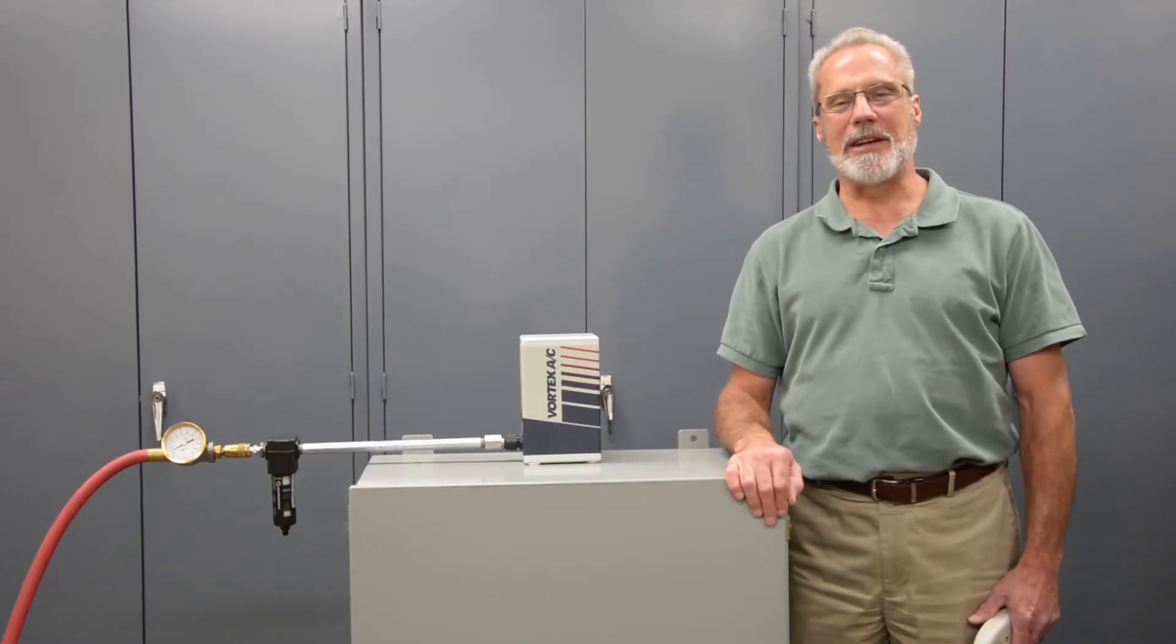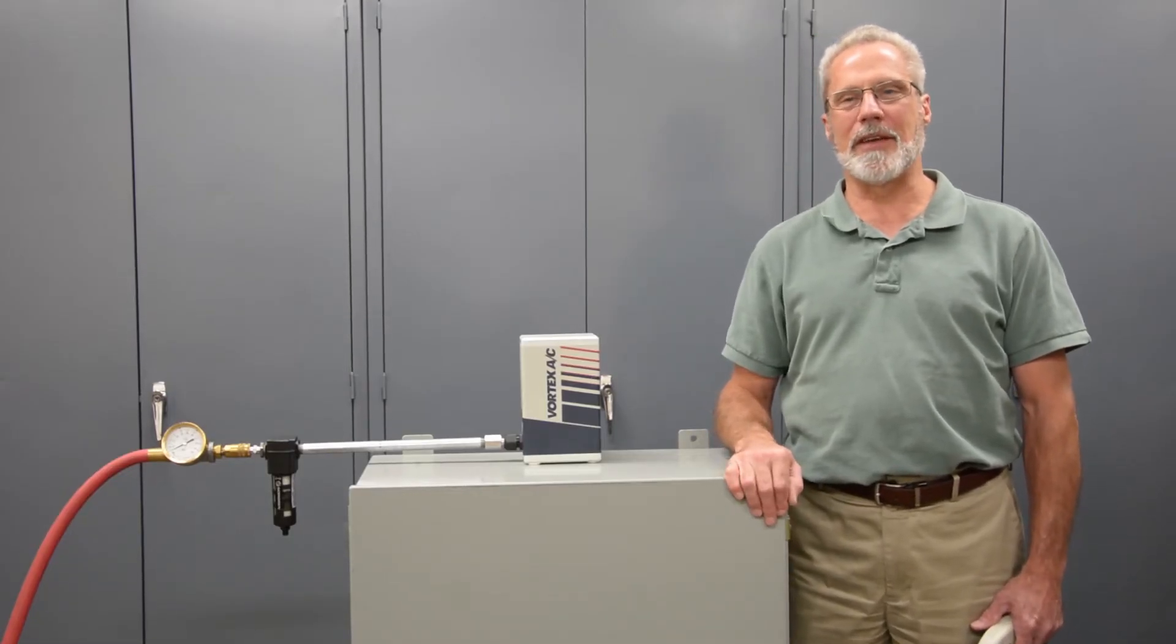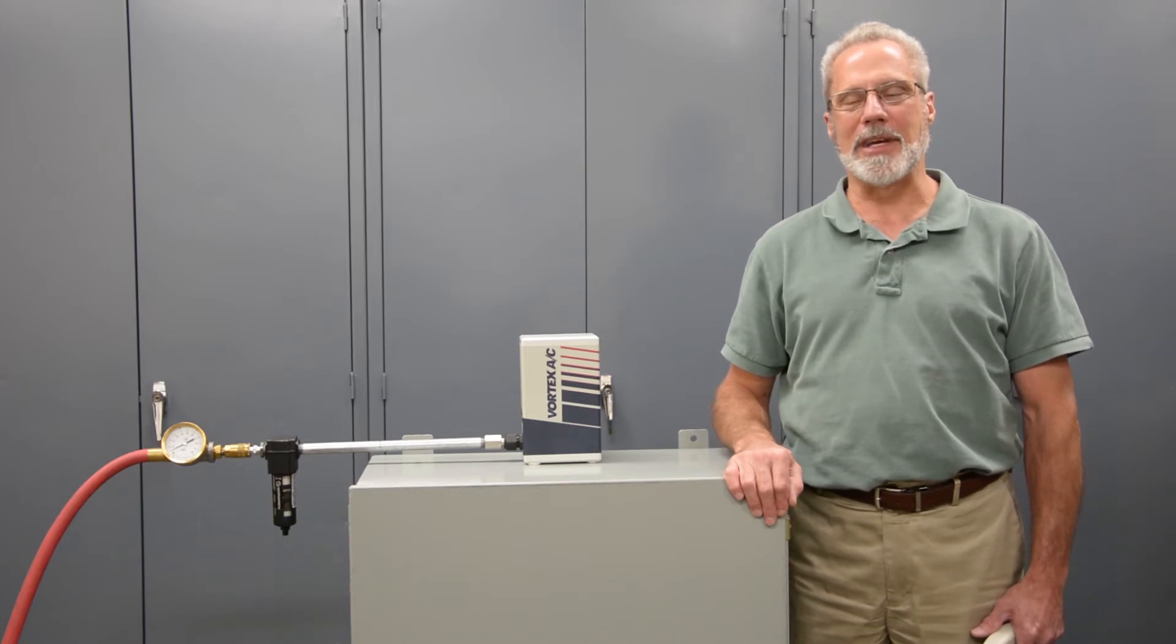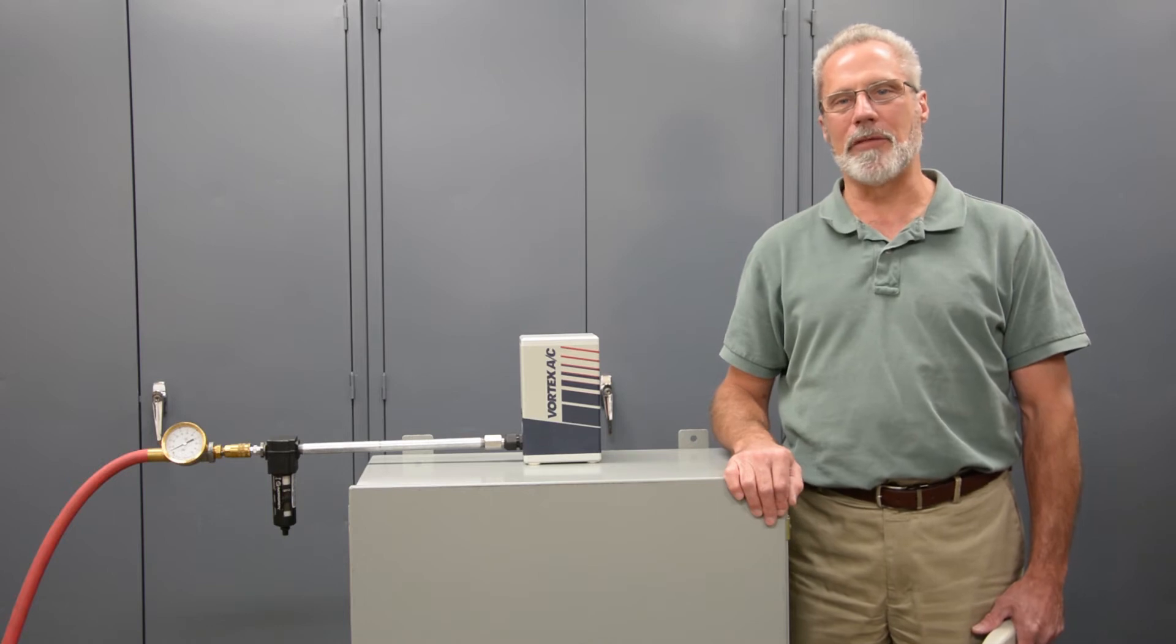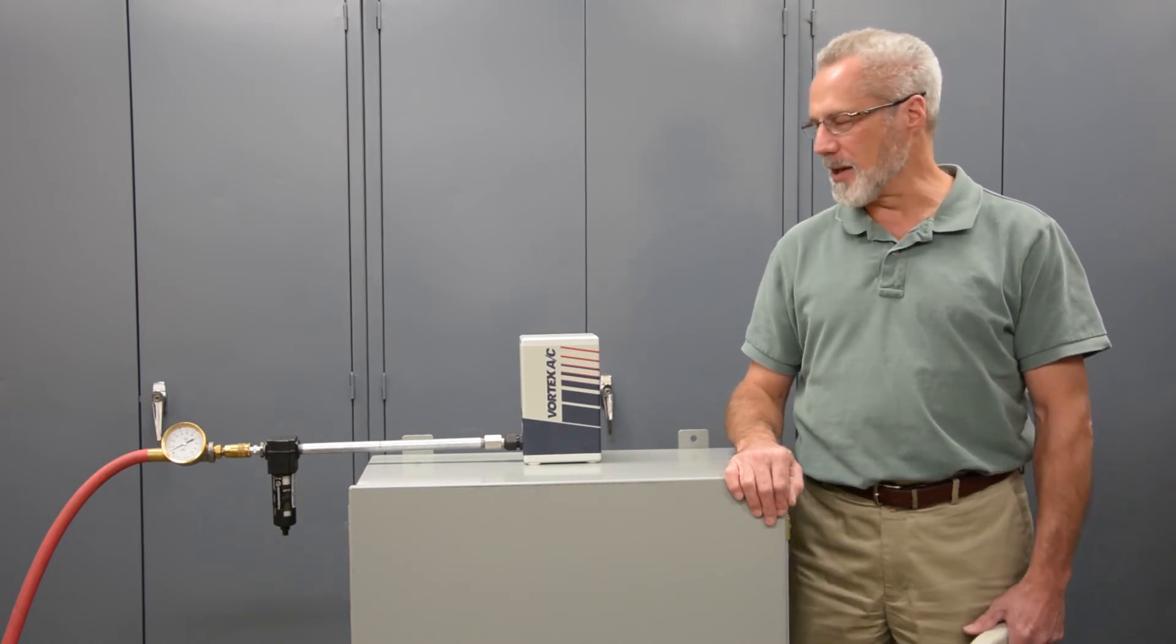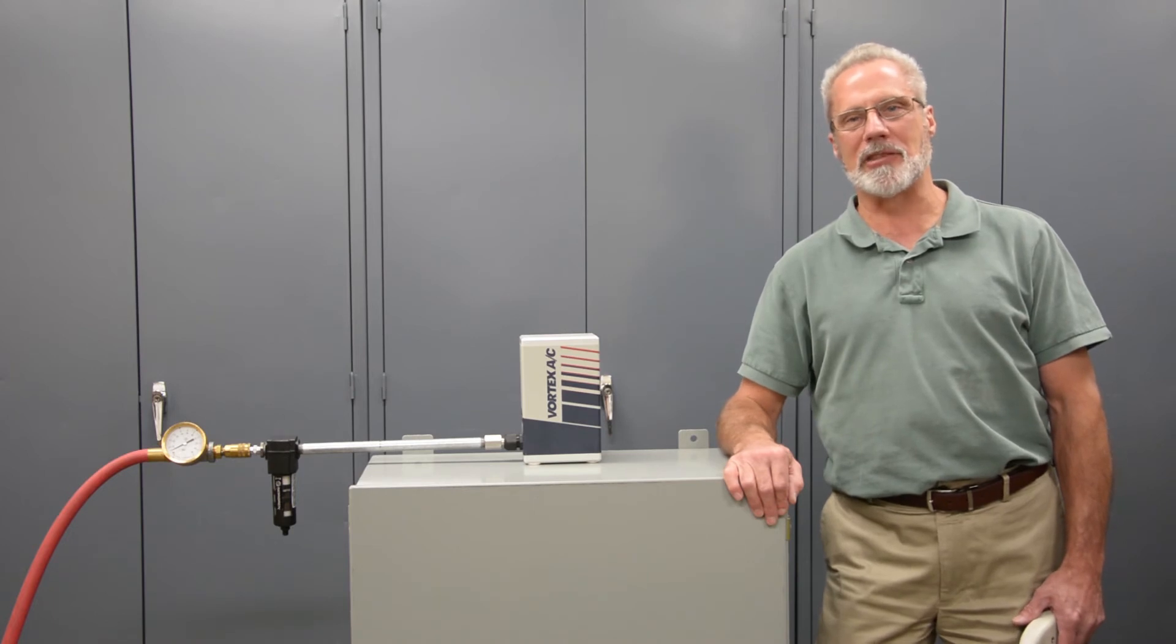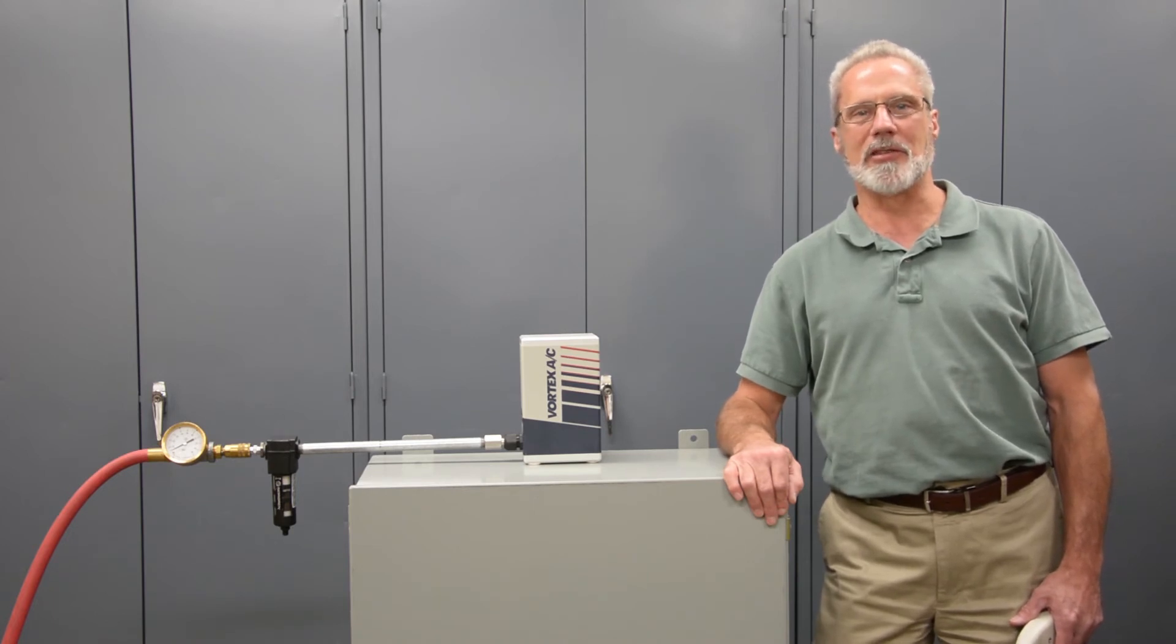Next I'm testing an ITW Vortex model 7725 Vortex AC which is a 25 CFM cooler rated NEMA 4 and 4X. We're running this at 90 psi air pressure under the identical conditions that we tested the competitor's unit at.